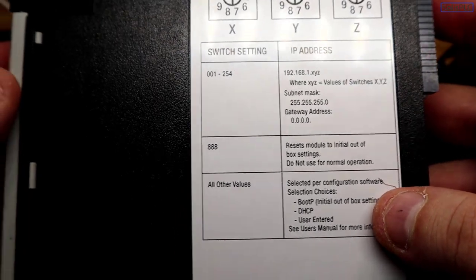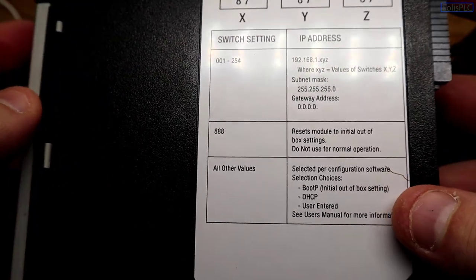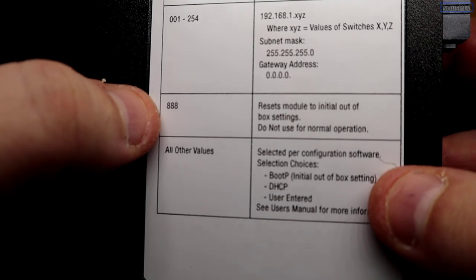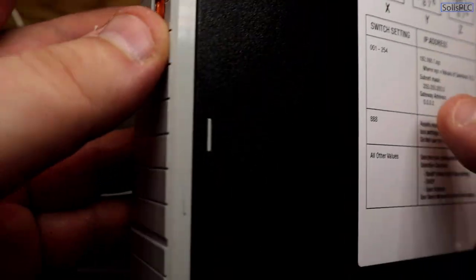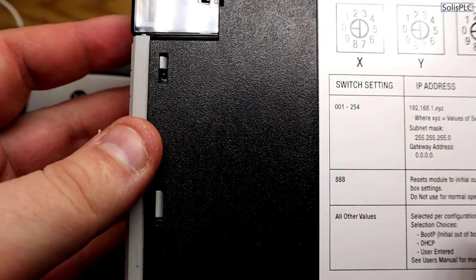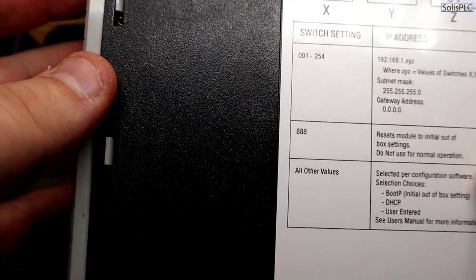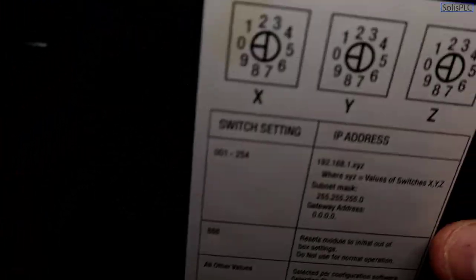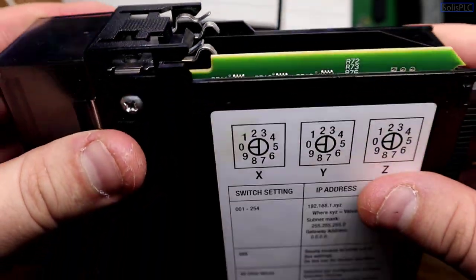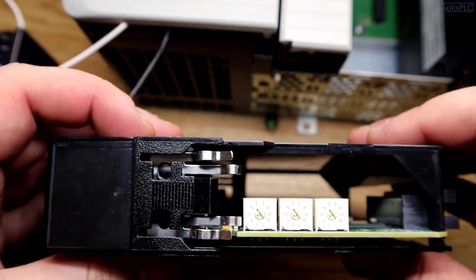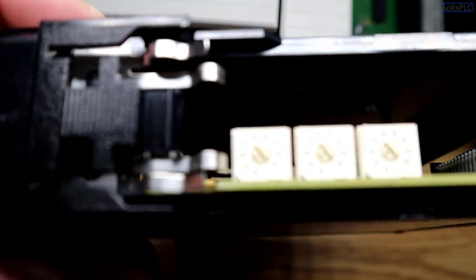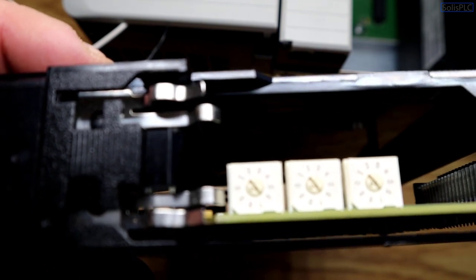Now, the method that can reset the card to its default setting is going to be this 888. In case you were paying attention, this card was already set to my private network address, which was 192.168.1.11, I believe. So I'm going to look at these rotary switches, and I'm just going to push the rack out of the way so you can focus and see a little bit better. You'll see that the switches are located at the top of the card, and you can actuate them through the use of a small flathead screwdriver, which is what I have here right now.